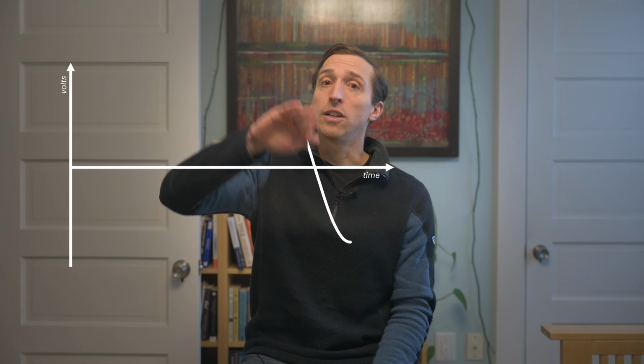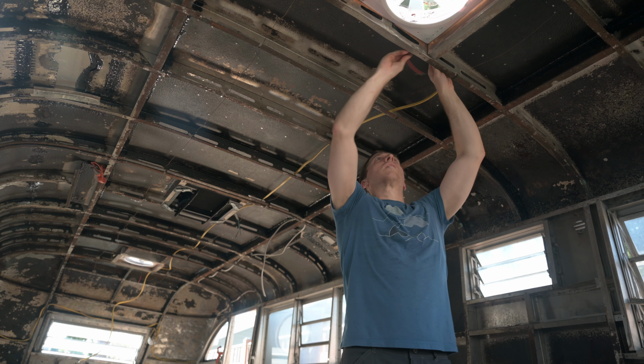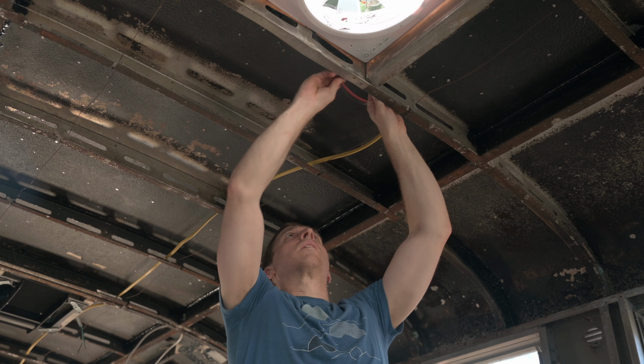Whereas AC is alternating current, and the voltage goes up and down very quickly. DC current doesn't travel through wires as well as AC, so I'm using the 12 gauge cable here to help it as much as possible, even though the fan is very low power at 10 watts. That means it's less than 1 amp of DC current. You can take a look at tables like this online to figure out how big your cables need to be for DC powered devices, depending on how long the cable is. For the purposes of this video, it's enough to say that this 12 gauge cable works for these fans.